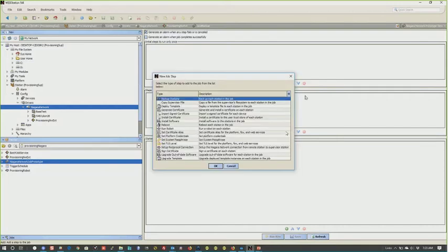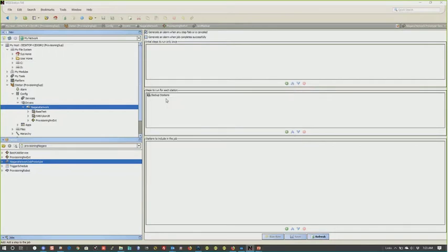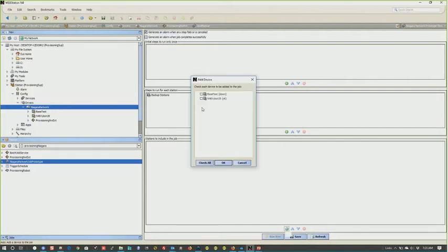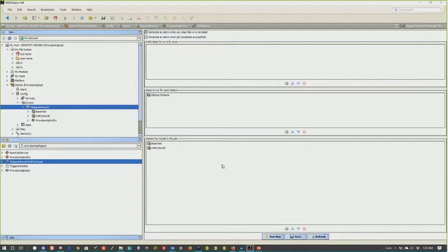So when you hit the plus, you can see there's an extensive list there of things that you could add to that. So in our case here, we're going to back up stations. And then the bottom part is what stations do we want this job to apply to. So then from there, it'll give you a list of all the JACEs that are within your Niagara network. I'll select them, or you can hit select all and hit OK. Then from there, you can test it, and you can say, okay, I want to run it now.